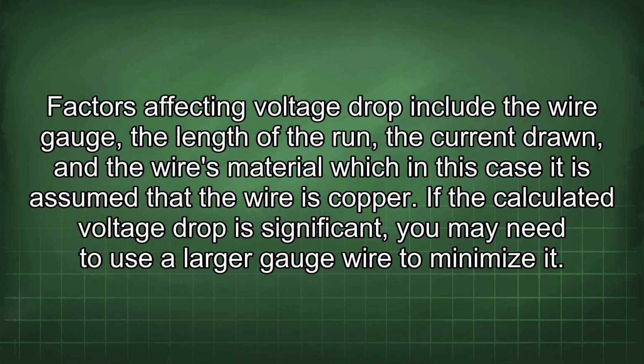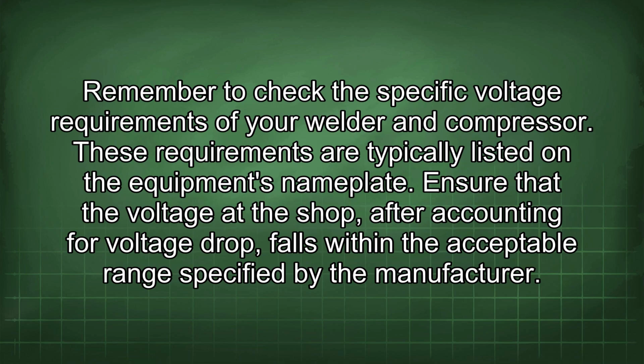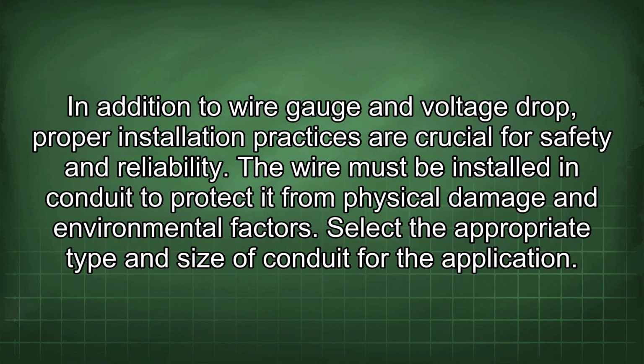Factors affecting voltage drop include the wire gauge, the length of the run, the current drawn, and the wire's material, which in this case is assumed to be copper. If the calculated voltage drop is significant, you may need to use a larger gauge wire to minimize it. Remember to check the specific voltage requirements of your welder and compressor. These requirements are typically listed on the equipment's nameplate. Ensure that the voltage at the shop, after accounting for voltage drop, falls within the acceptable range specified by the manufacturer.